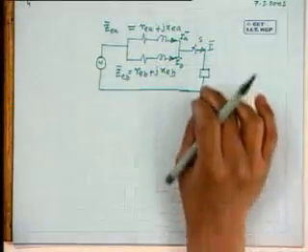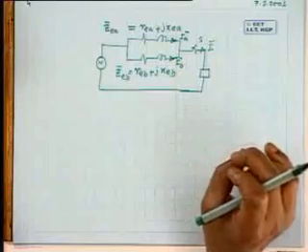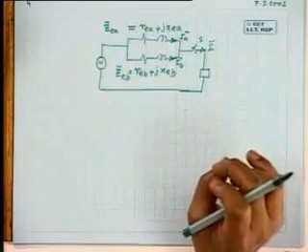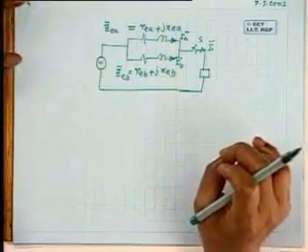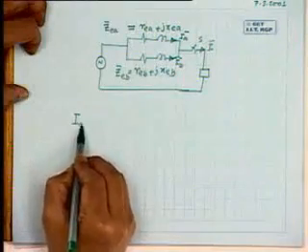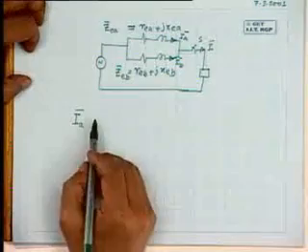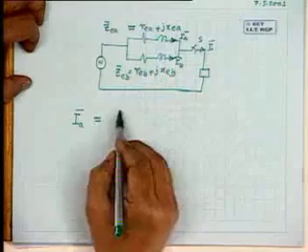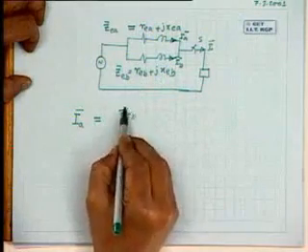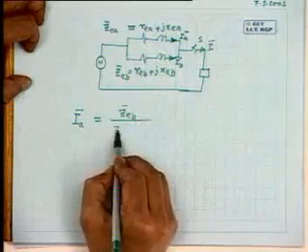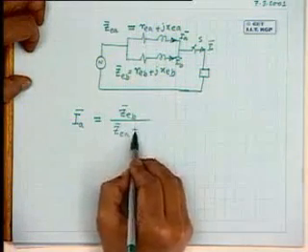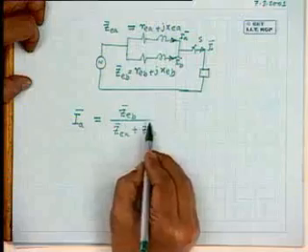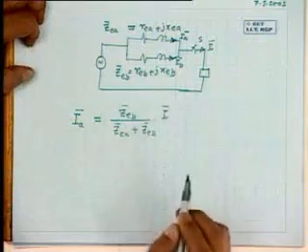So what we are really trying to do is find how much of the total current delivered to the load will be shared by either of the transformers. That is why we are trying to find the expression of the current. This can be easily found by applying the parallel current distribution law. To calculate IA bar, it is the other impedance ZEB bar divided by ZEA bar plus ZEB bar, into the total current.